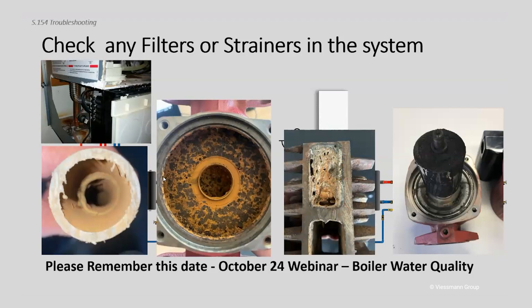If you want more information on water quality in boilers, we have a webinar coming up on October 24th that will cover this. It's an important part of S154 when we have issues with flow through the boiler. The water might look clear when you're opening it up, but like Brita filters — there are contaminants you don't see that build up over time and cause issues. A poly B system, an old boiler sitting inside that poly B pipe — if we don't clean that system properly when retrofitting, we could have a problem. Same for lined old cast iron sections. There's going to be legacy from that old system that could be reintroduced if we don't properly flush it out.